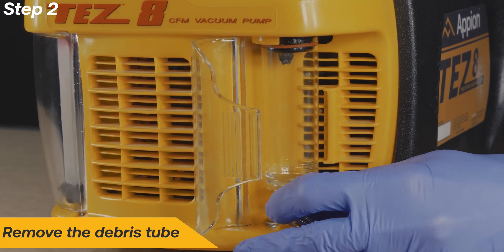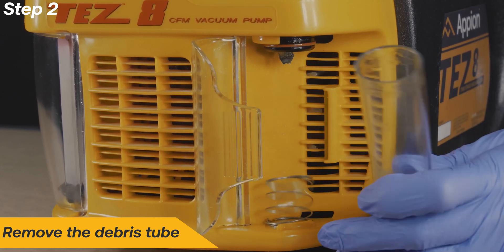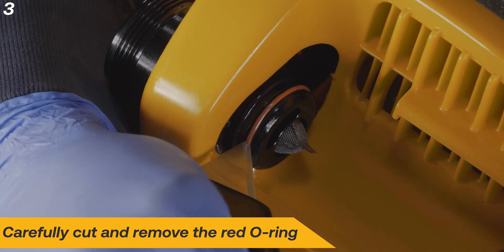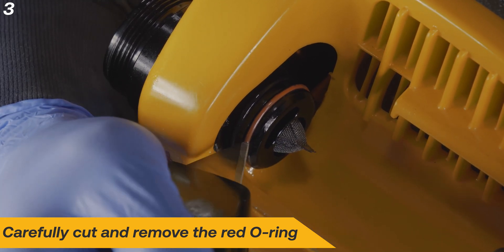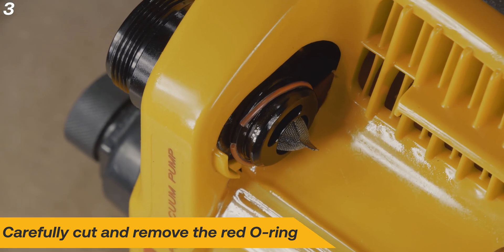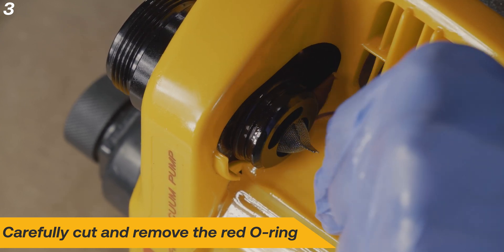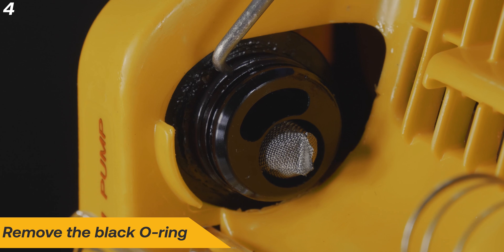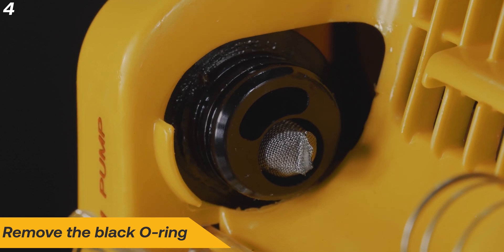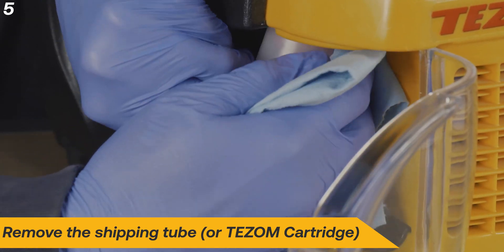Remove the old debris tube. Use a razor or utility knife to carefully cut the red O-ring to remove it. Take care to avoid damaging the sealing surface of the fitting. Remove the old black O-ring with a pick. Remove the shipping tube or TEZOM Cartridge and set aside.